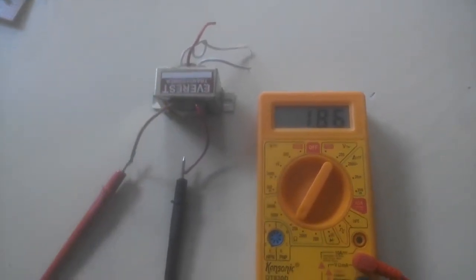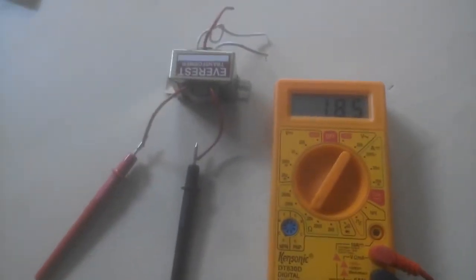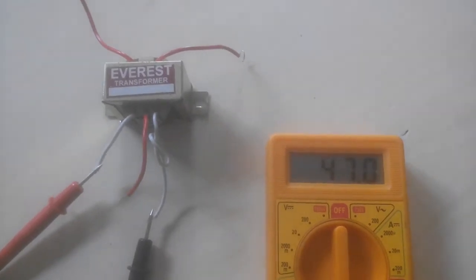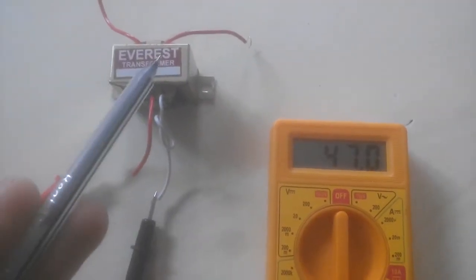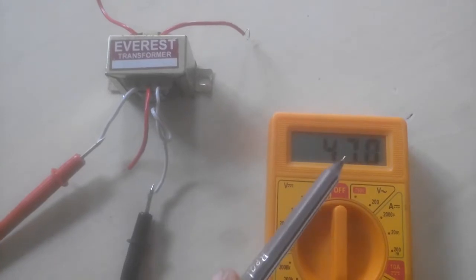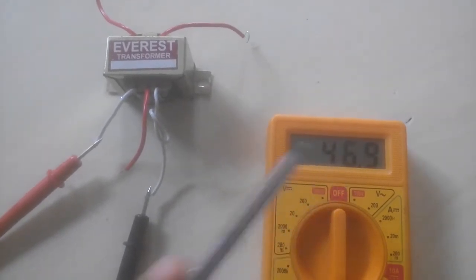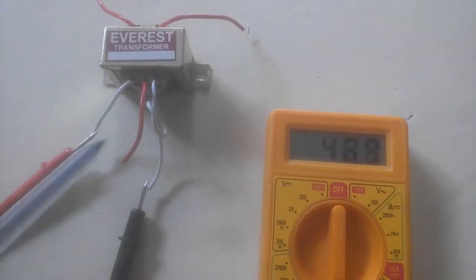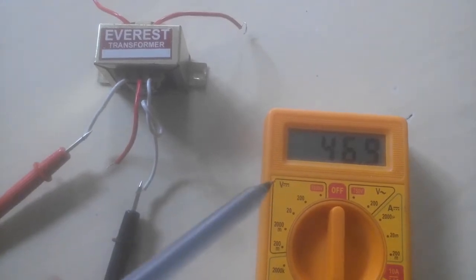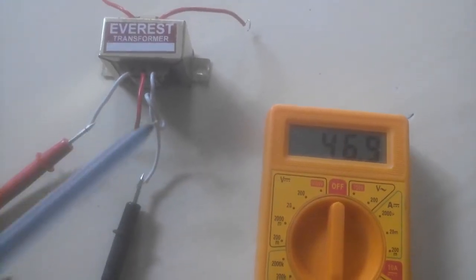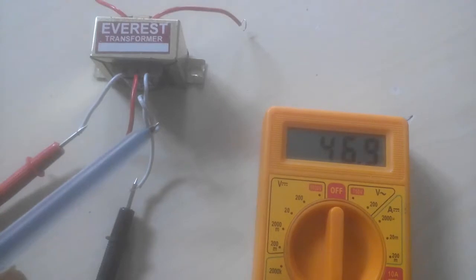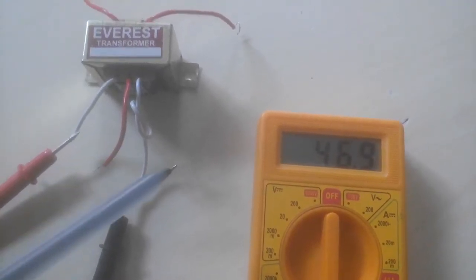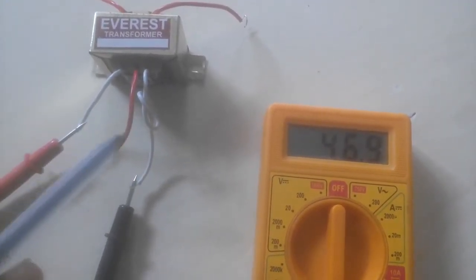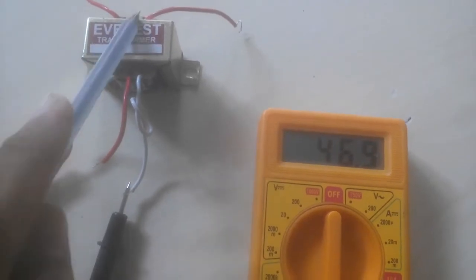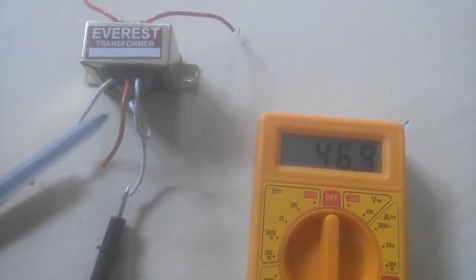We can also test the secondary side. Let us do it. As we can see, I connect the secondary of the transformer, and this reads around 47 to 46, where its resistance lies for the secondary. So the secondary side has less resistance as there are fewer turns. So we can say this is the secondary and this is the primary terminals of the transformer.